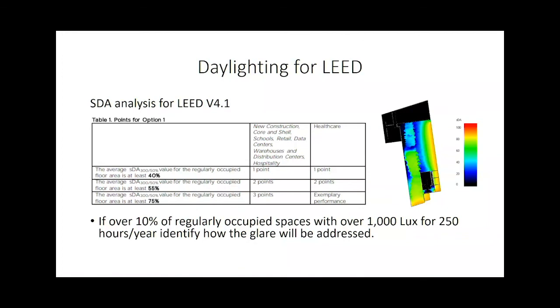The one other requirement in LEED 4.1 is if over 10% of your regularly occupied spaces have greater than 1,000 lux, you're going to have glare issues as a result. So if over 10% of your spaces have more than 1,000 lux for more than 250 hours per year, you have to provide a narrative saying how the project is going to address the glare issues.